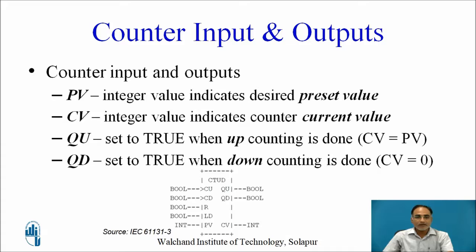PV is an integer value indicating the desired preset value. CV is another integer value indicating the counter's current value. QU is the output of the counter, set to true when up counting is done — that is when CV becomes equal to PV. QD is the output set to true when down counting is done — that is when CV becomes 0.